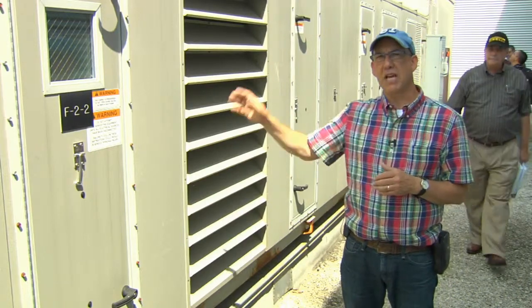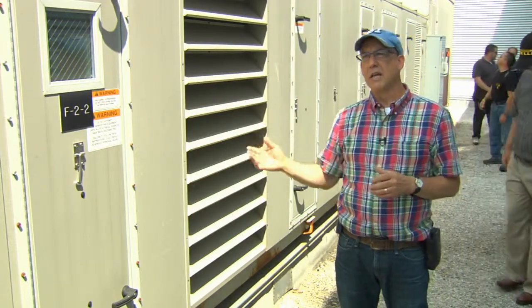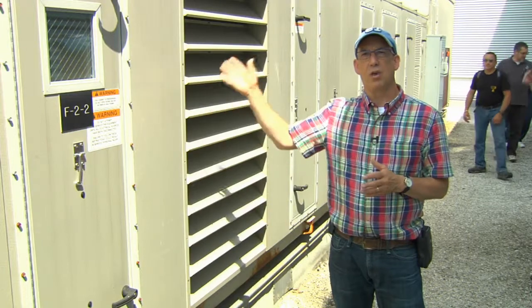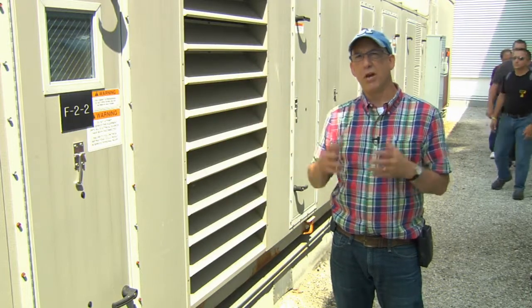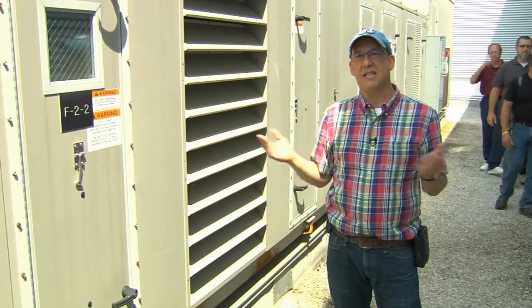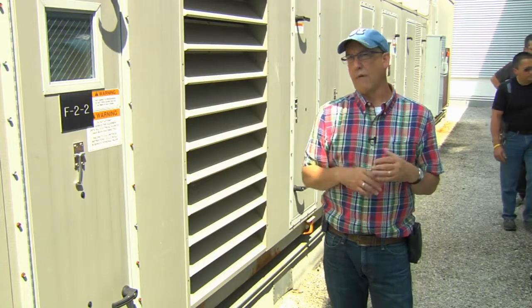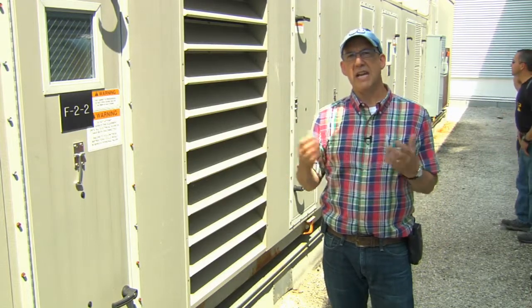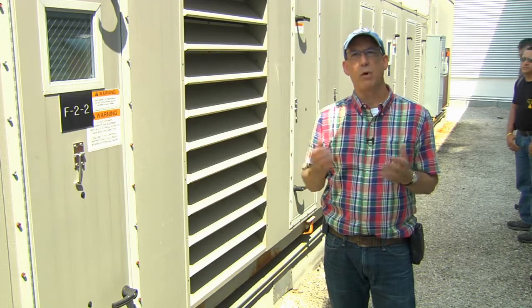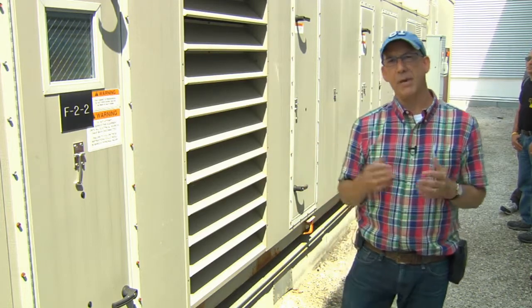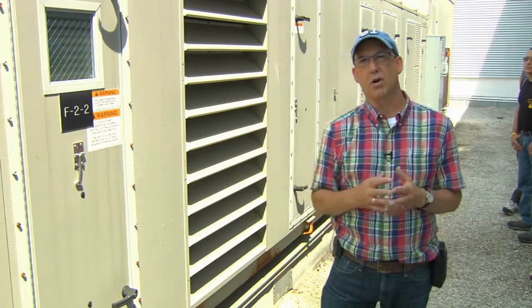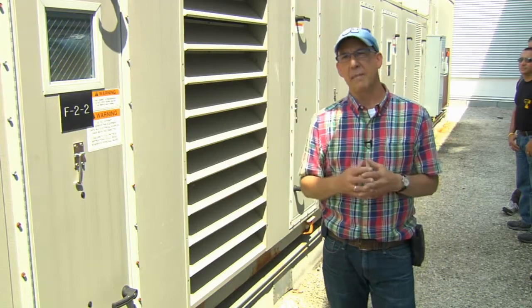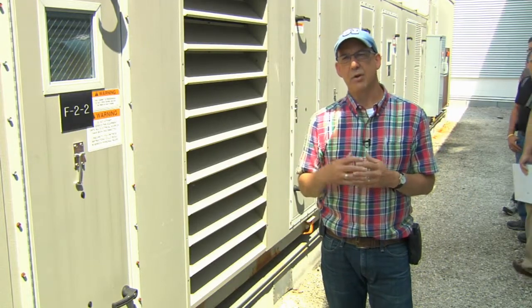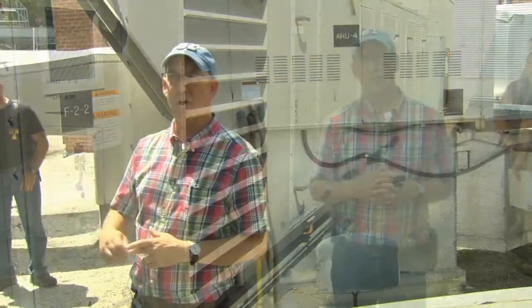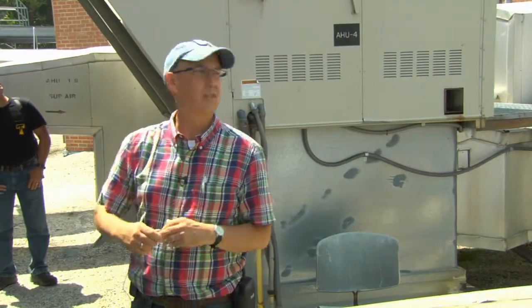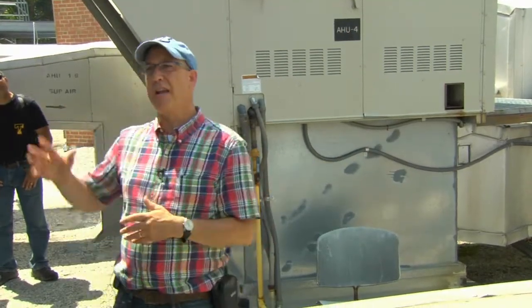The same thing that we're seeing on air handler after air handler is your minimum outside air is always wide open, and we don't know if that's an excessive amount of outside air or if it's not enough. We don't see any CO2 sensors, so that might be something we would recommend. It would be a cost issue, would be to upgrade your controls to have demand control ventilation and reduce your outside air.